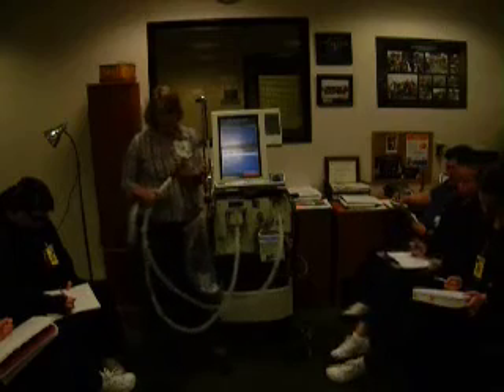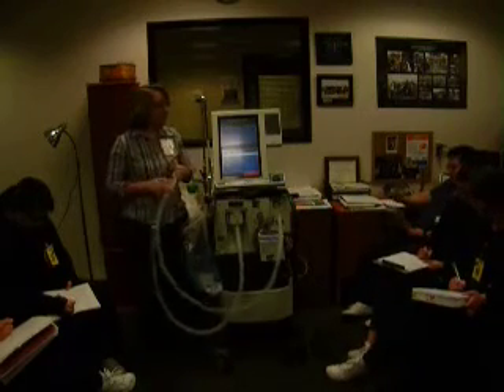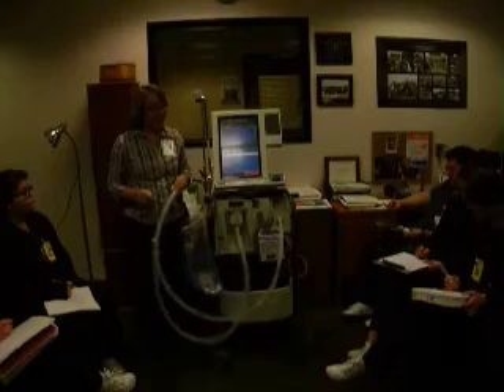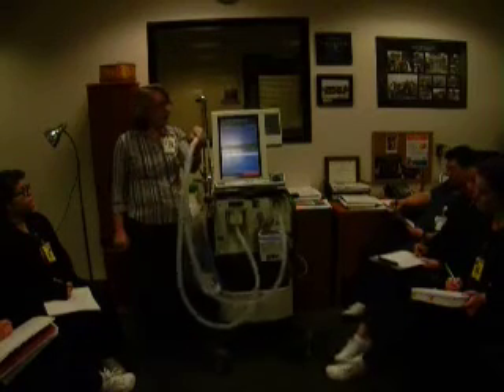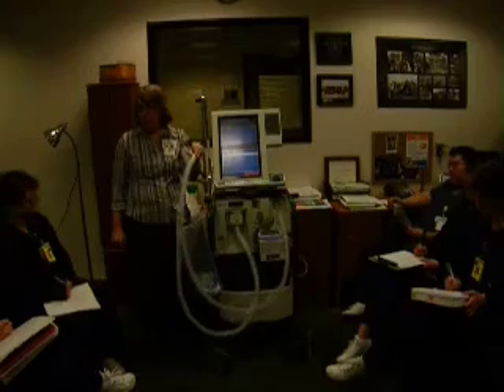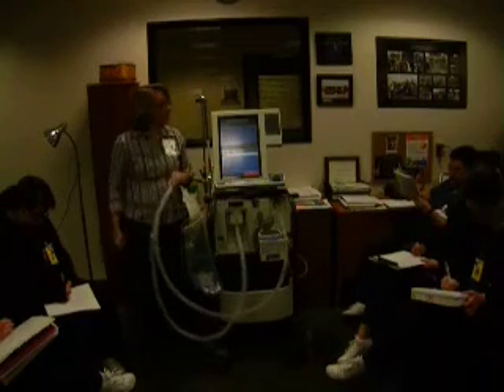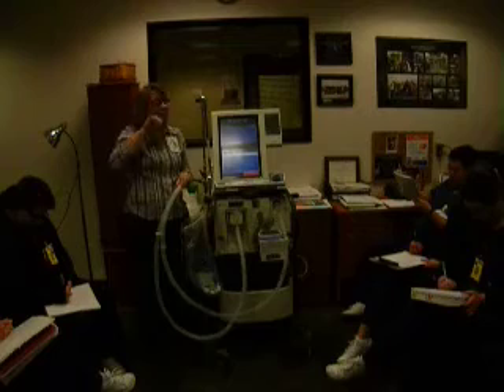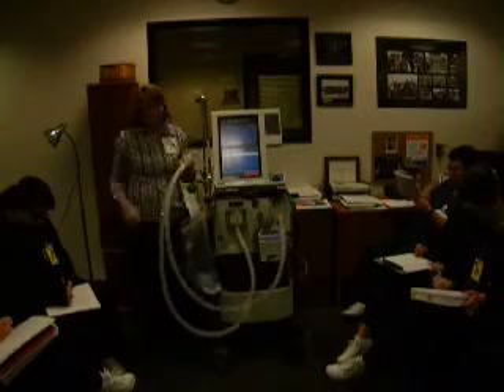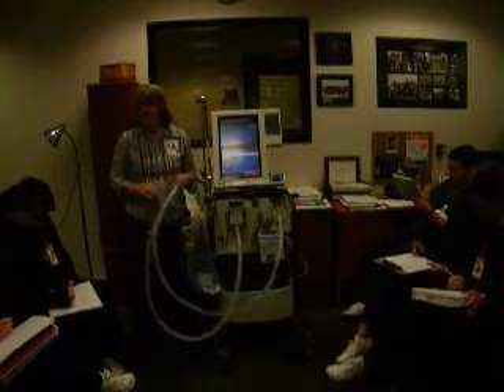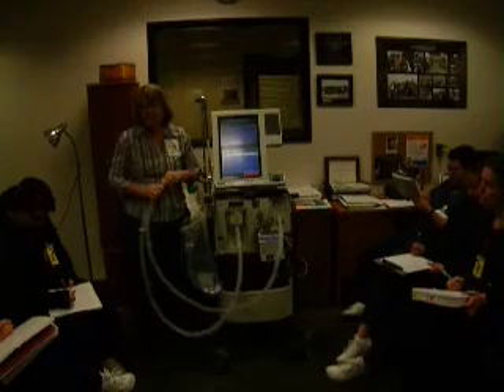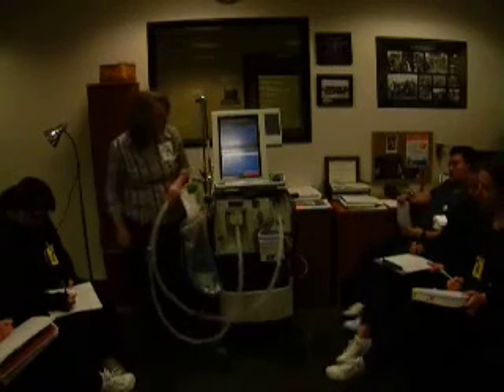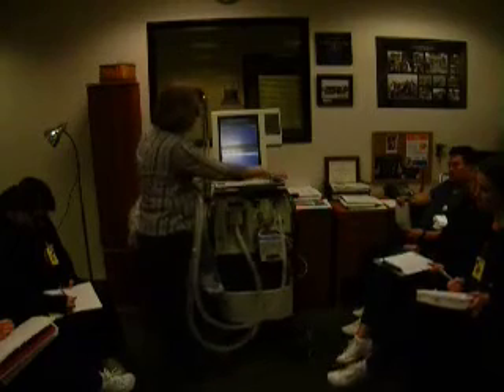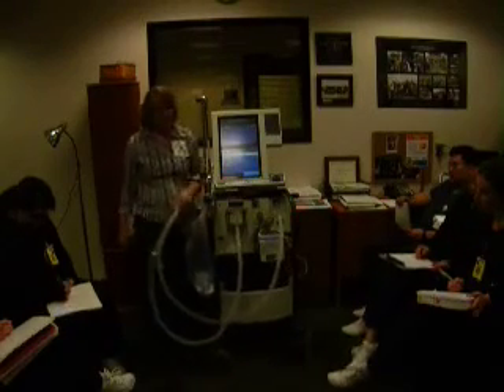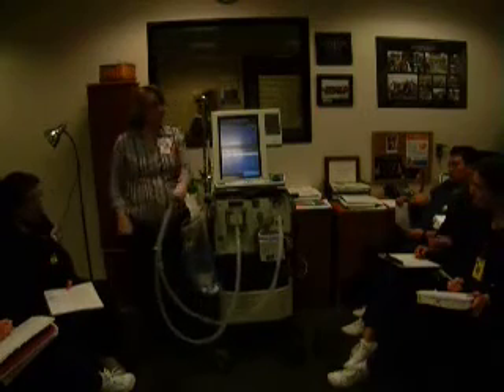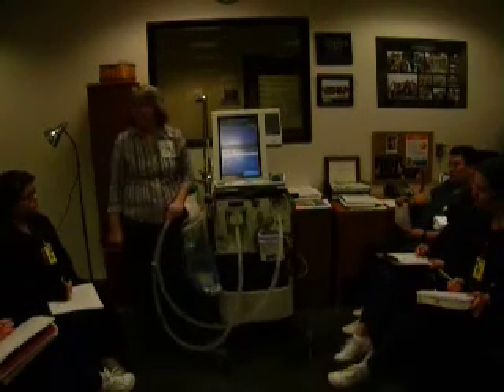Now it says block Y. One of the most important things with this ventilator and what everyone makes the mistake of, when it says to block the Y, do not unblock it until it tells you to. Doesn't matter if you go through 6 steps. You can go step to step to step. Don't unblock it even in between steps until it tells you to. If you do, you will fail. You'll fail your SST, and if you can't pass your SST, you can't go on to ventilation. So it says block Y, when done, press accept, so I'm going to do that. And now it's going to continue. And we have little covers for the circuits that you could use because you can see my hand's going to be exhausted by the time I'm done.